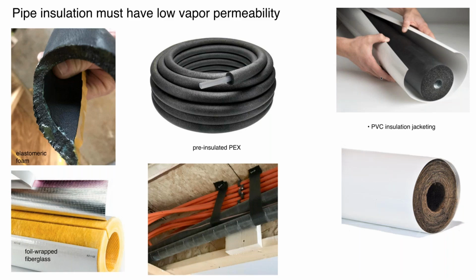It's readily available. When you use it, it's important that the seams are glued together properly, as well as the butt joints. There are companies that sell pre-insulated PEX. We have used this on projects. It's really nice. You can run this from basically a basement mechanical room up to an air handler without having to piece together all the individual 6-foot pieces of elastomeric foam. It's available from 1/2 inch all the way up to 2 inch.